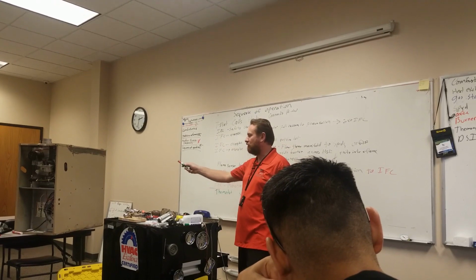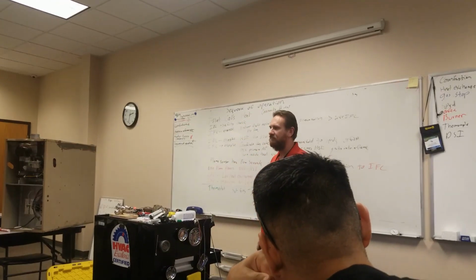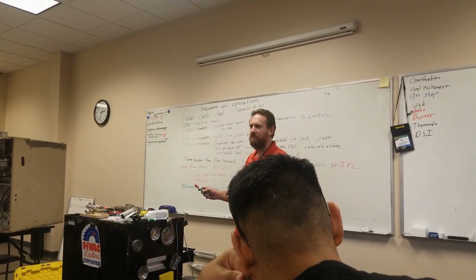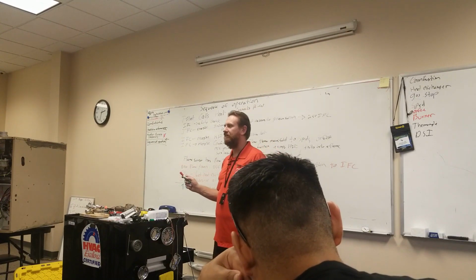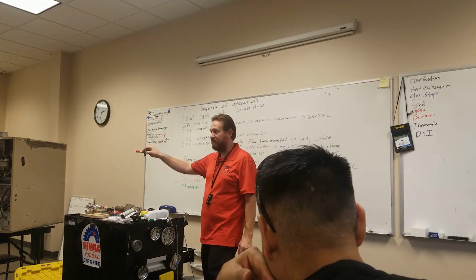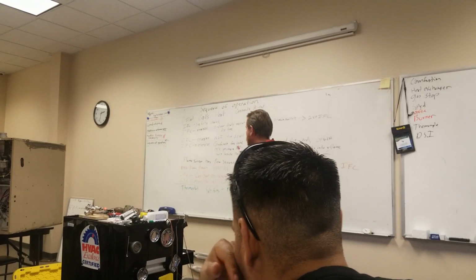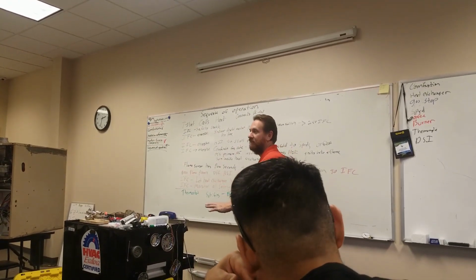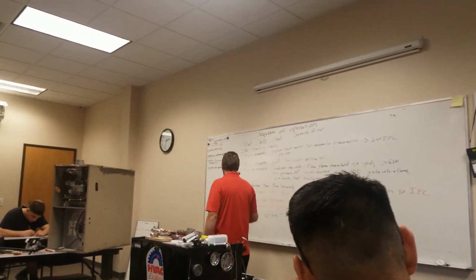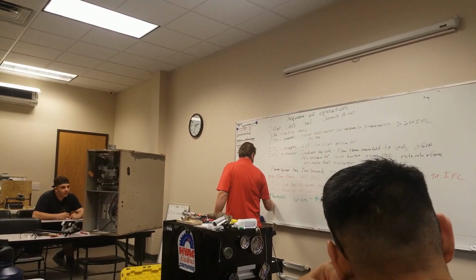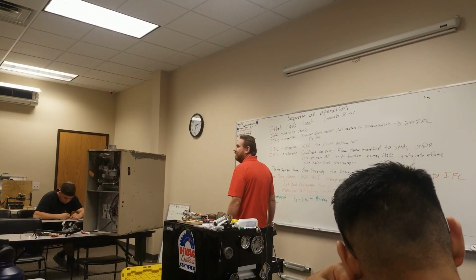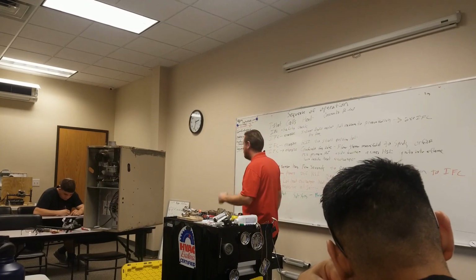Does the thermostat control the fan on heating cycle on this unit? What controls the fan on heating cycle? The unit itself, the control board, the IFC does. The thermostat just says, hey, I need heat or I don't need heat. So once the thermostat satisfies, guess what the IFC does? It immediately kills the combination gas valve.